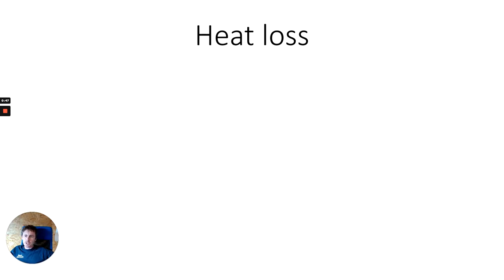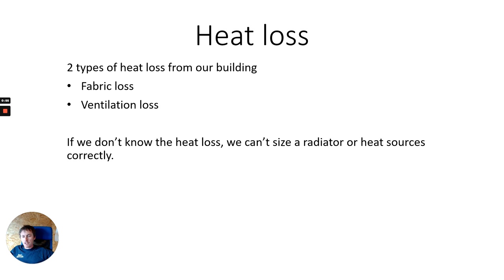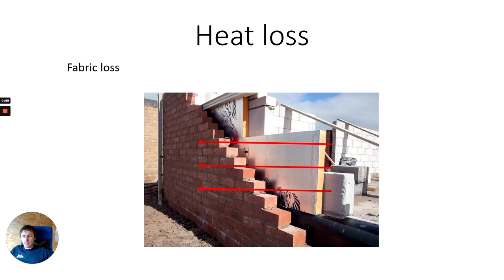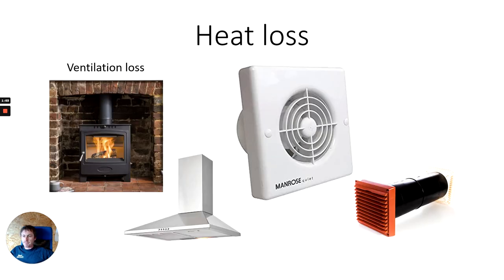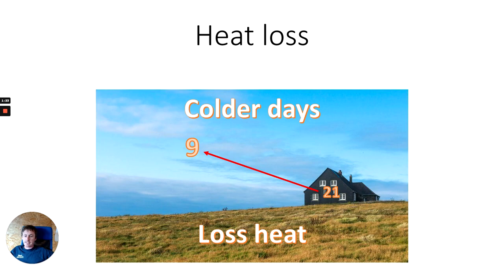There are two types of heat loss for a property: fabric loss and ventilation loss. If we don't know the heat loss, we can't size a radiator or heat source correctly. Fabric loss is what's physically passing through all your walls, the fabric of the building, windows, etc. Ventilation loss covers things like log burners, flue liners, kitchen ventilation, bathroom ventilation, and purpose-built ventilation in the brickwork itself. On hotter days your property will actually be gaining heat from outside, and on colder days you'll be losing heat to outside.